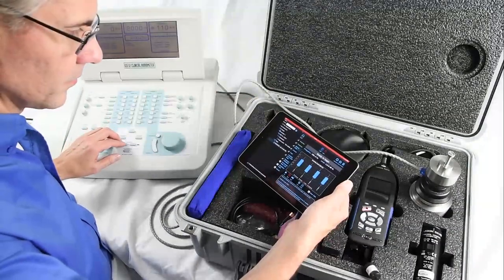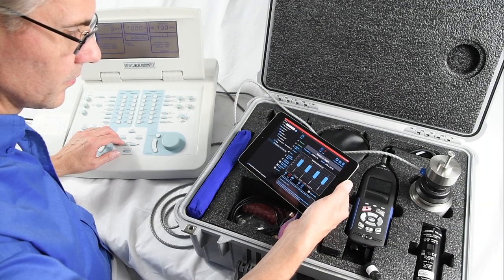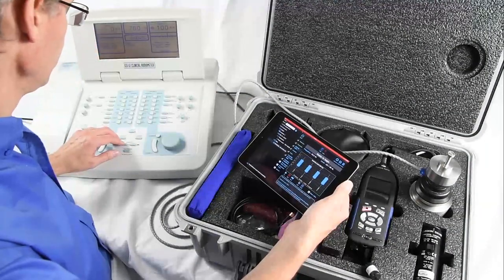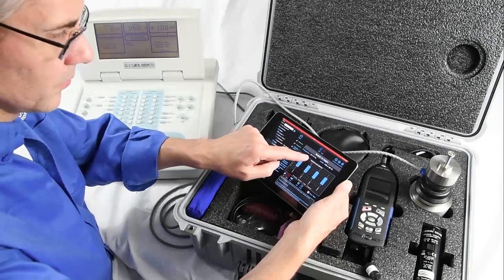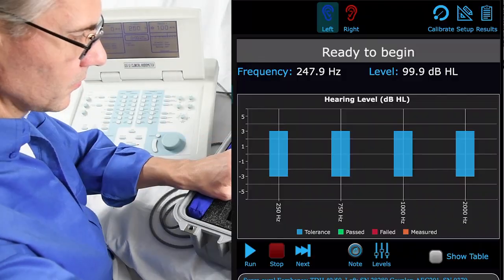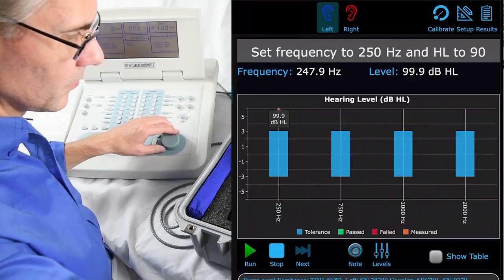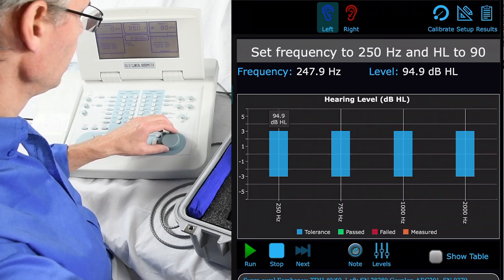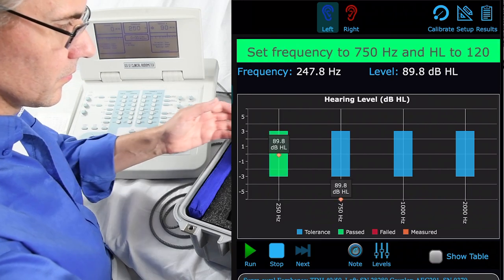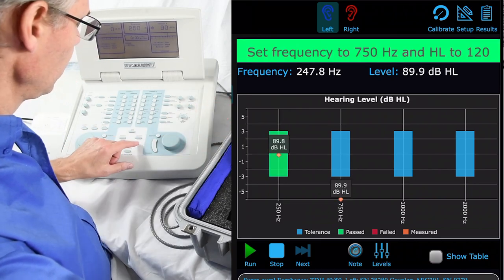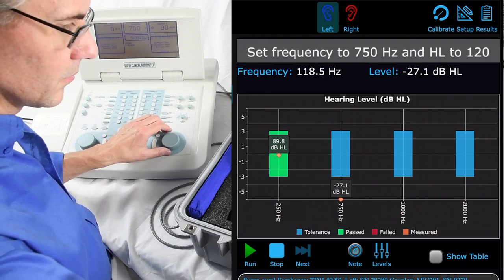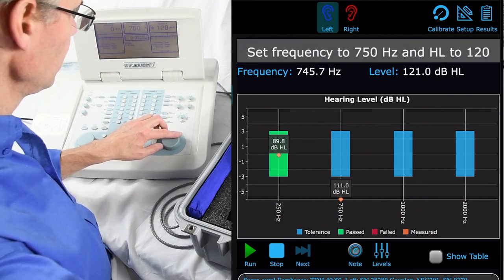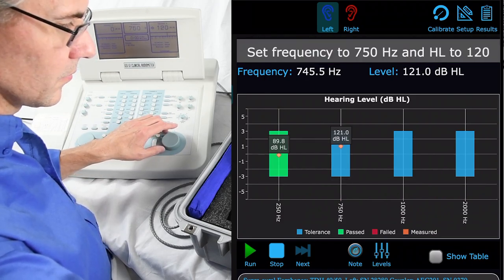Brent is checking the current level for the hearing level test before running. You can see the live display of data at all times on each page. As soon as one step is passed, you can change to the next step. Brent doesn't need to wait very long to turn the dial or set the dB HL — he can keep his hand on it and turn as each frequency passes.